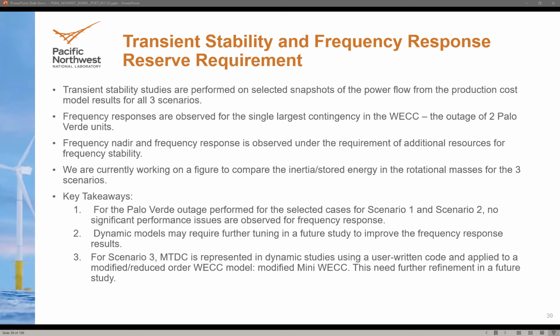For scenario 1, the HVDC or HVAC radials, and scenario 2 with the HVDC radials, we were able to get more or less good results with respect to frequency response. We performed the single largest contingency outage in WECC, the outage of two Palo Verde resources, and looked at the frequency response following that event and how the offshore wind performed.